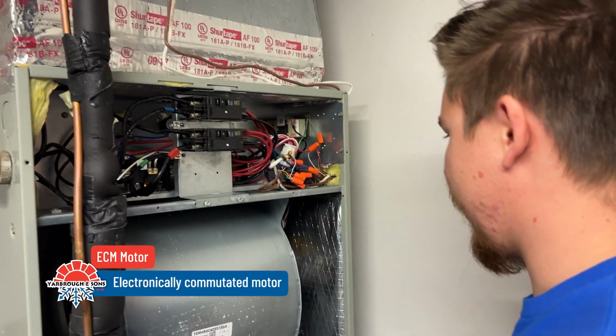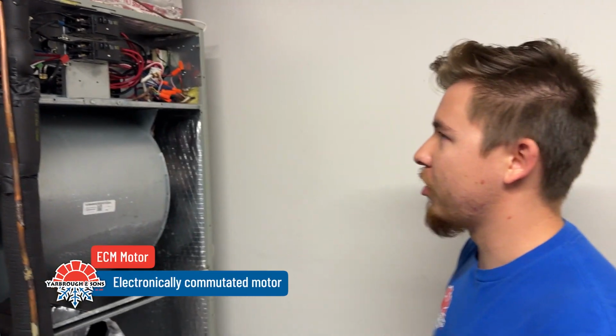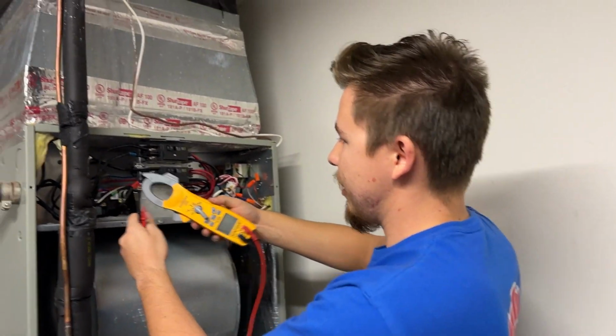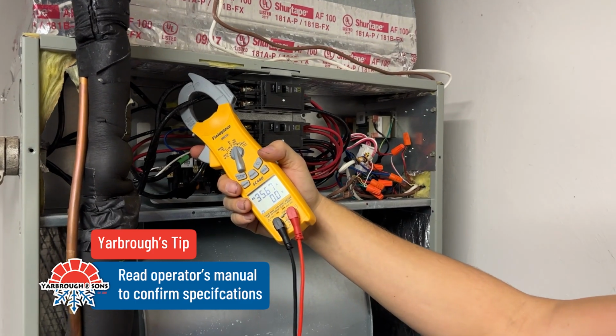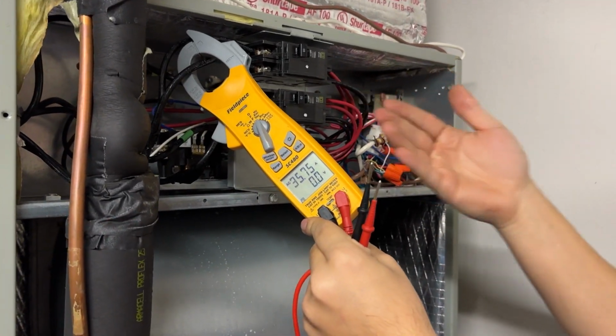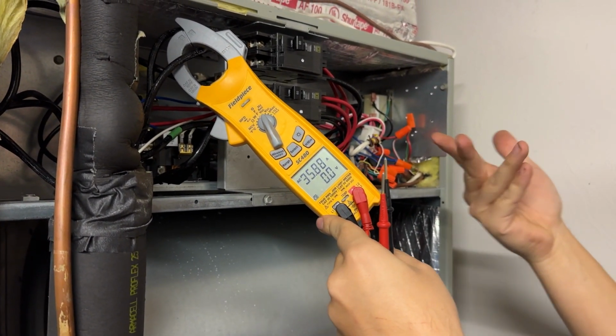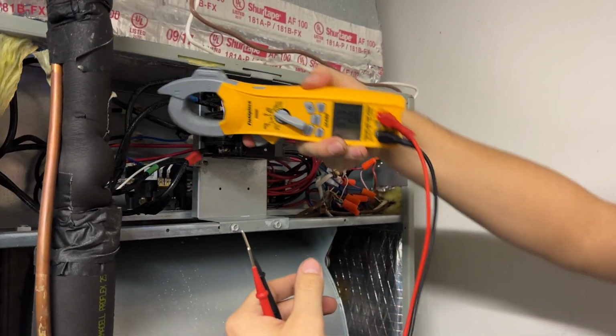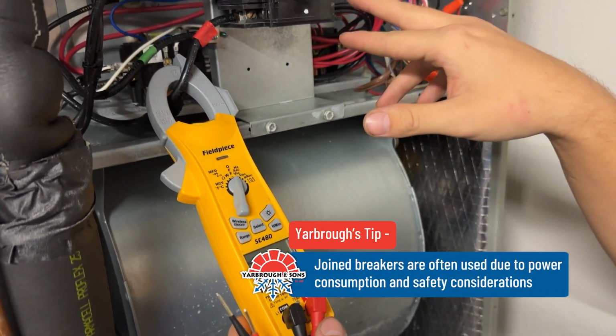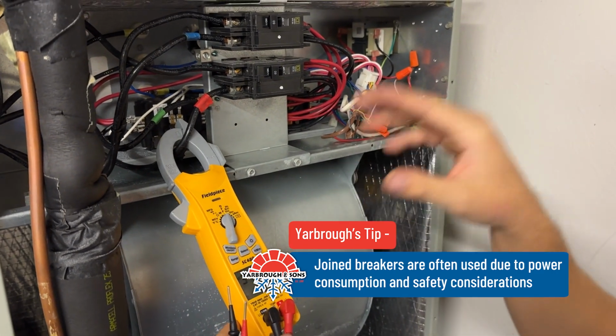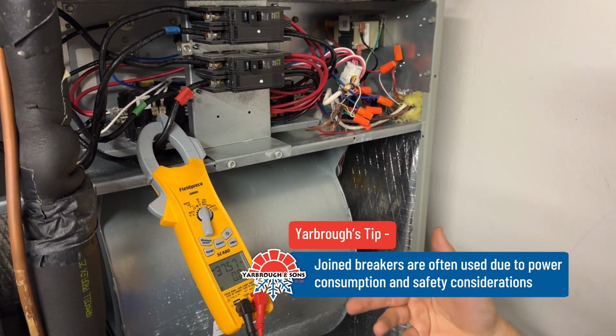Thermostat on, have the breakers turned off. It's going to ramp up because of the ECM motor, no capacitor. We're just going to wait a little bit. Sometimes they do have it on instantly. You want to have around 20 amps. So 35, because they are joined in together, it should be around 40, but 35 with it just now turning on is perfectly normal. We're going to let it run. Same with these ones. These two are joined in together. This is two separate breakers or two separate heat strips. So this is about 37, they're joined in together.